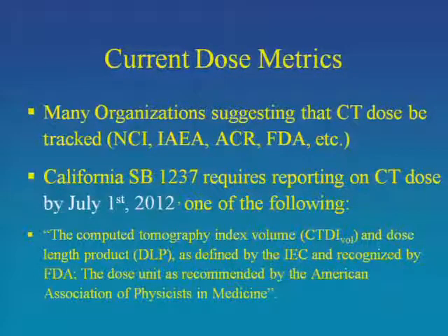Inpatient, outpatient, freestanding clinic, academic medical center, doesn't matter, but we have to record the CTDI and dose length product as defined by IEC and recognized by FDA, or, thanks to John Boone, we can record the dose unit as recommended by the AAPM. So we actually get some say in this, and that was meant to give us some leeway to move from CTDI to things like dose equilibrium or something, whatever we're going to do from TG111 and TG200.